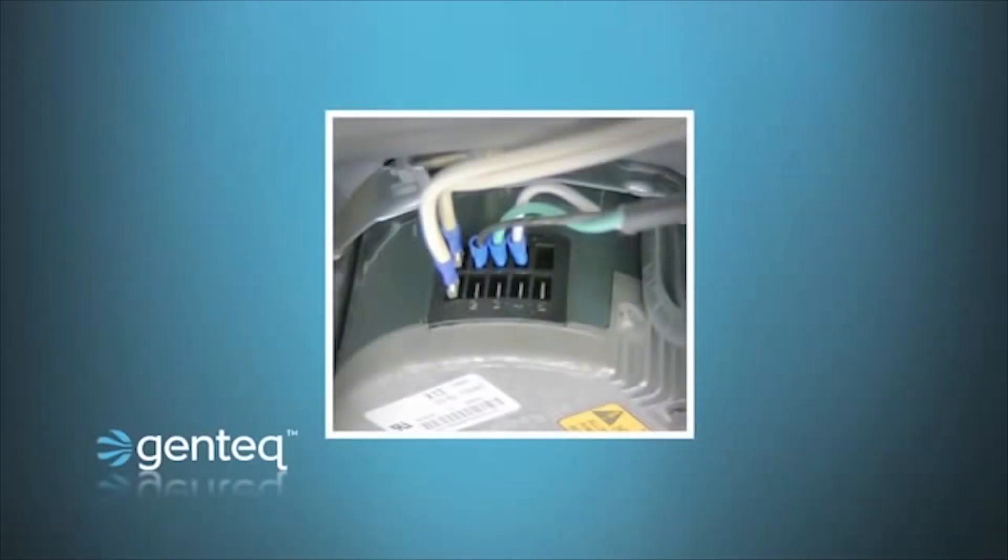Now with all that said, the manufacturer does not have to use these plugs and some may not. Here we see a picture of a package system that is gas only, therefore there's only one tap programmed and no need to use any plugs or connectors. Simply use what we call flying leads to each one of the places on the motor that power and communication are required. Since only one tap is programmed and none of those leads will ever need to be moved, this is a perfectly acceptable way to connect the motor.